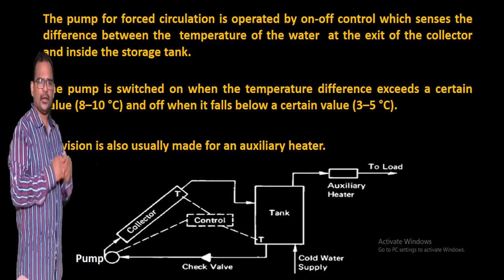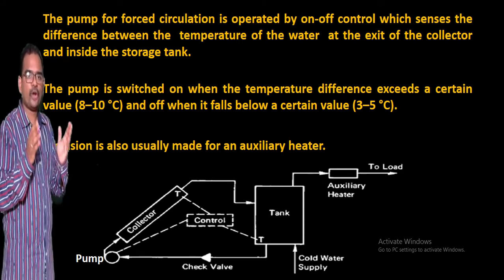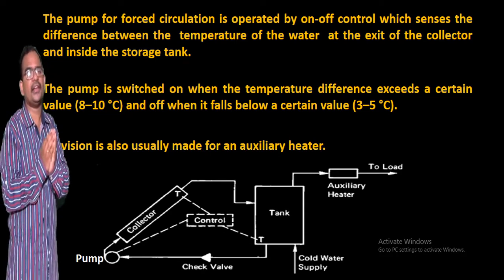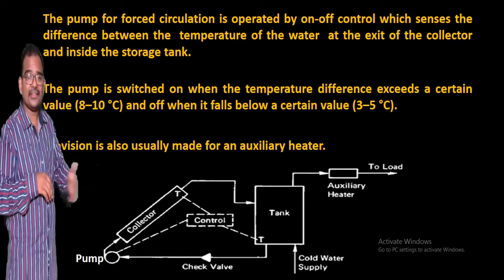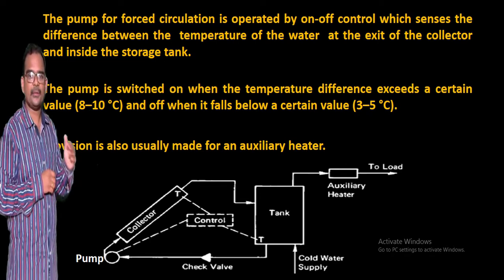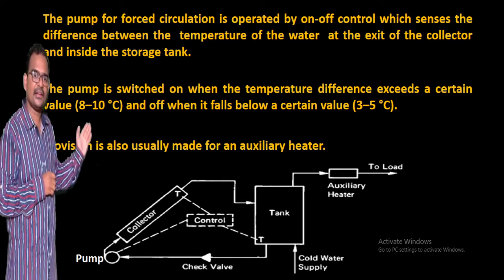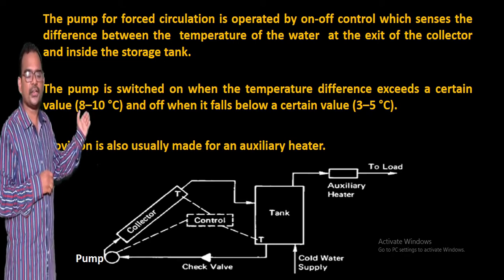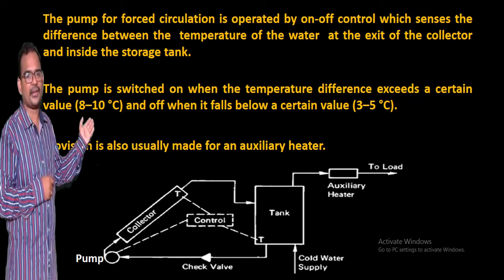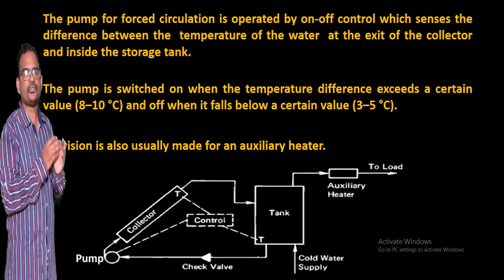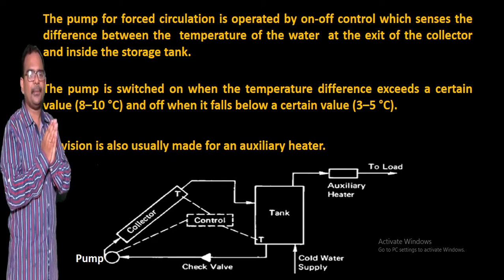On the other hand, if the temperature difference is between 3 to 5 degrees centigrade, it means the tank is heated up and the water inside is also heated up, so there is no need to send the water into the collector again. The controller automatically sends a signal to the pump to turn it off, as there is no requirement for hot water since the temperature inside the tank is within the prescribed limit.